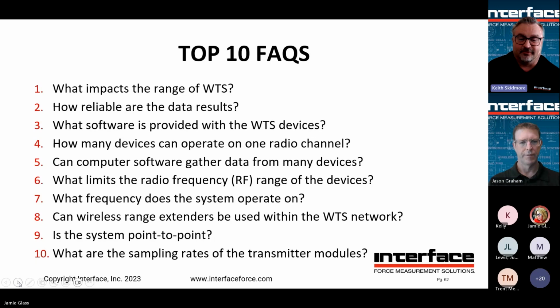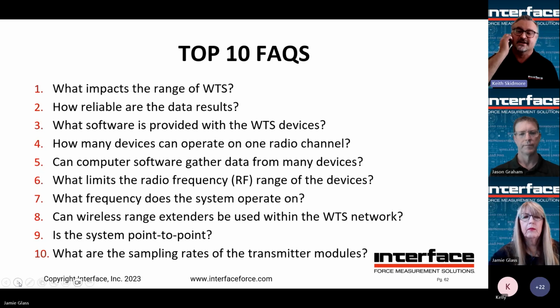Yeah. And sampling rates, typically it's up to 200 per second on the WTS, and that's limited. Again, that's also the rate limit of the channel. So if you have 2 sensors on the same channel, you can't each be set for 200 per second. They'd have to be set for 100 per second. We do have some faster options. There's a high-speed transmitter in the WTS lineup that transmits at 2,000 per second, but that basically consumes the entire channel, so you can only have one of those on a channel at a time. And then some of the other stuff, like the BX6, uses somewhat different technology, and we can do up to, say, a couple thousand samples per second on a single channel with that device.